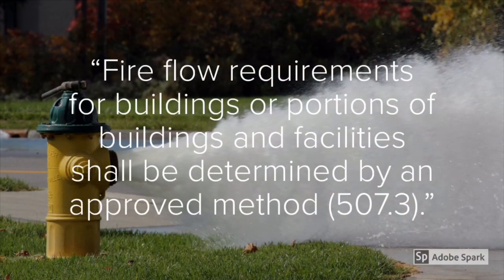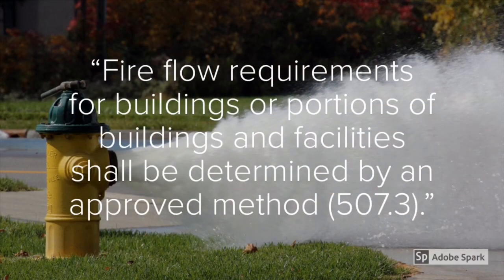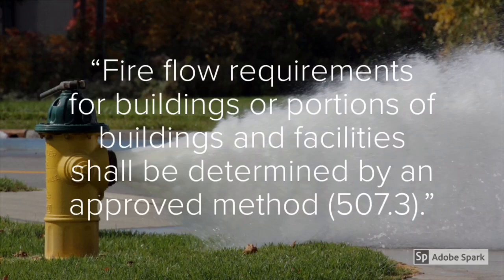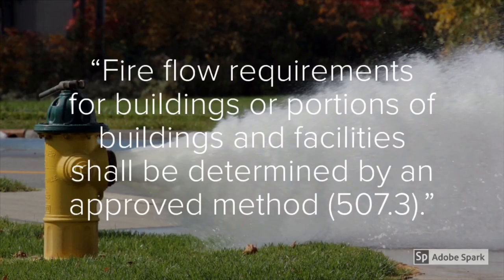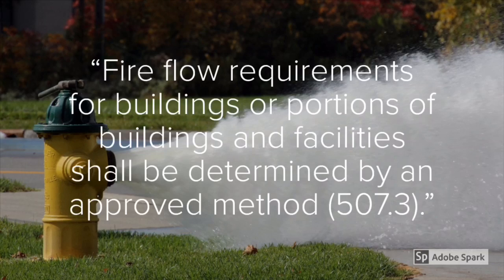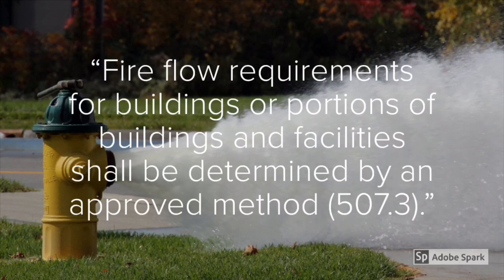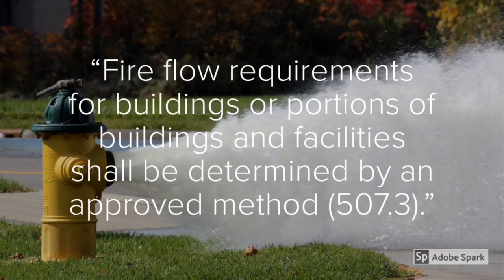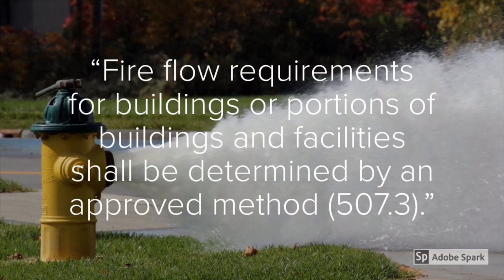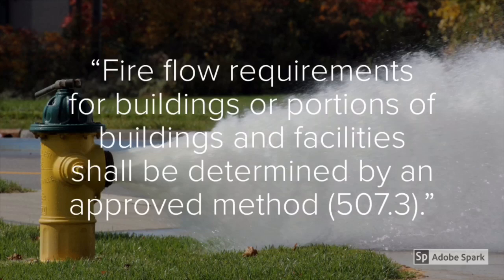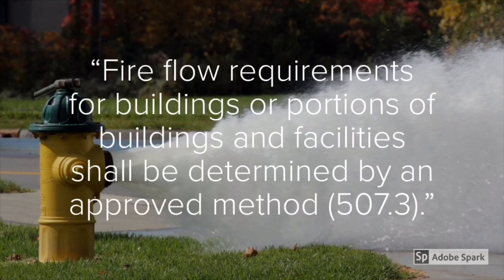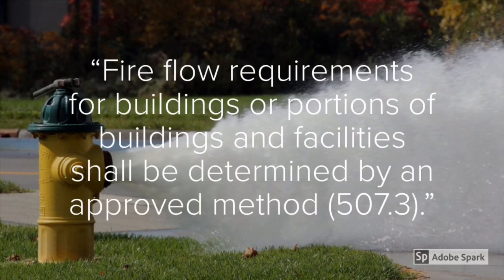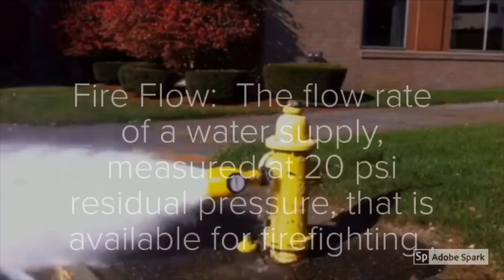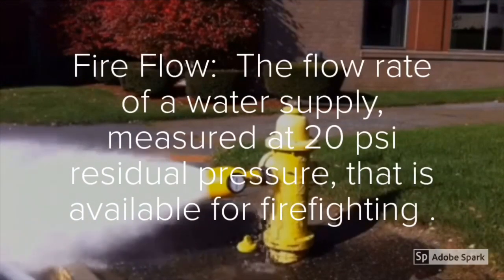Fire flow requirements for buildings or portions of buildings and facilities shall be determined by an approved method according to the International Fire Code. Appendix B of the Code is a good example of an approved method for determining fire flow and its duration. Table B105.1 bases fire flow on the type of construction and the square footage of the fire area. It is important to note, though, that the appendices are not considered part of the code unless specifically adopted. Looking at Appendix B, fire flow is defined as the flow rate of water supply measured at 20 psi residual pressure that is available for firefighting.